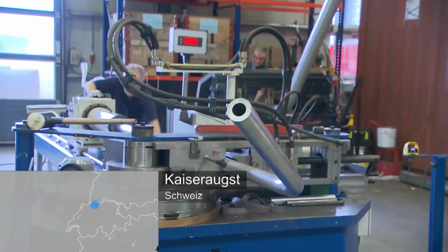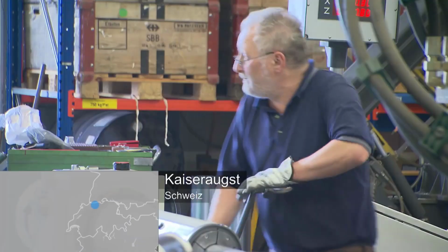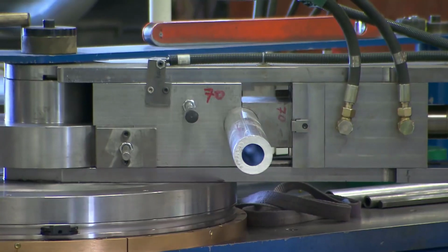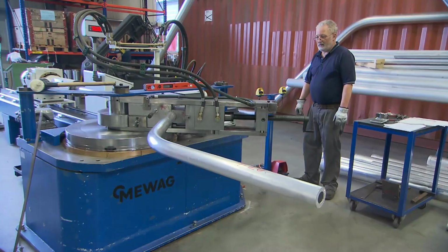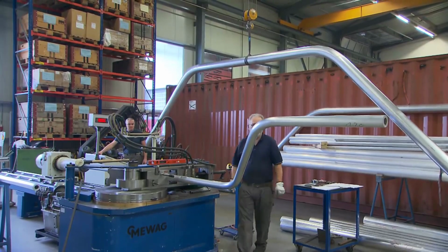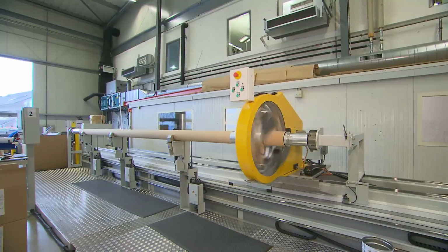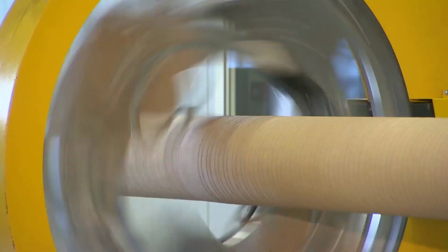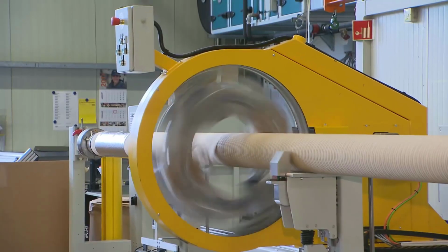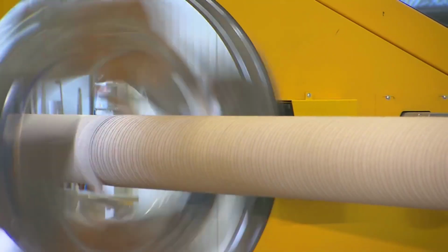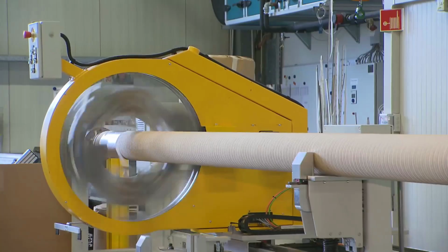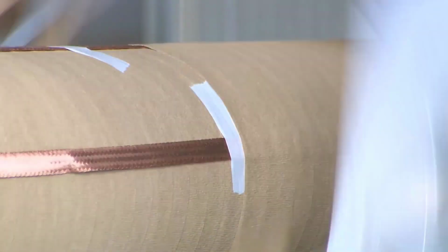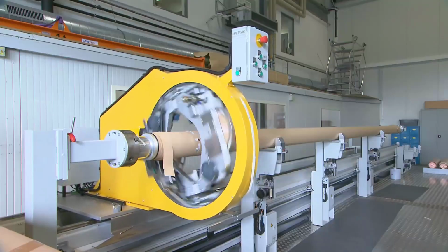Next is Kaiseraugst, near Basel in Switzerland, where Moser Glaser manufactures the bus bars, the connection between the generator and transformer. The aluminum conductors must first be bent to fit the future course in the cavern. Since the bus bar will transport electrical energy with a voltage of 14,000 volts and several thousand amperes during operation, it must be insulated in layers.